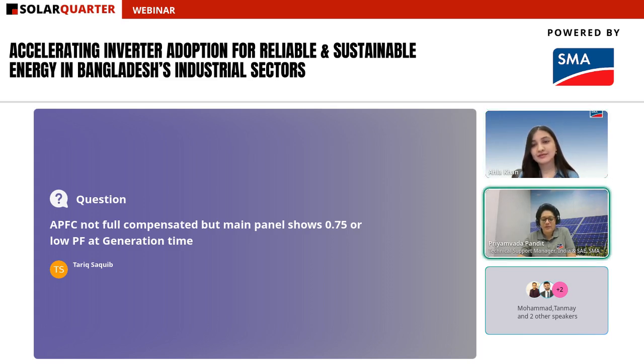Yes, so that is what I'm saying. Probably if you don't have an APFC panel, it will go further down. So the APFC panel is doing some of the work, but it's not enough. You can have both an APFC panel and PV in the system, but it is also important to understand where you have connected your PV. Your PV should be on the load side, and after that, your APFC panel should correct the power factor. Sorry, I said it the other way around. The APFC panel should be near the load side and then the PV.